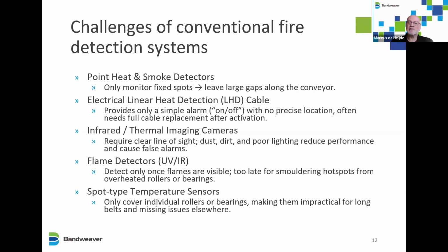Then we've got what I call traditional linear heat detection, which is basically two copper cables or two metal cables with a kind of glue in between. When the glue melts, it makes contact and sets off an alarm. It provides a simple on-off alarm and doesn't necessarily give you a precise location. And because the glue is melted, you will need to replace that section and sometimes the full cable after an activation. So if you get a lot of false alarms, this can become very costly.